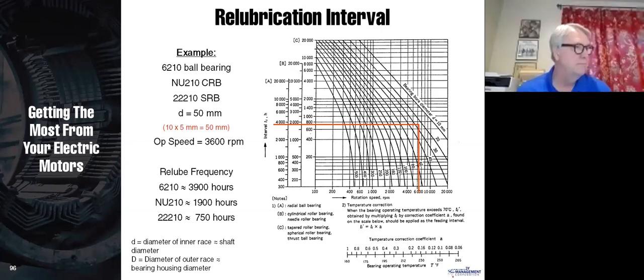Is it recommended to do body earthing on all types of motors? Yeah, so when we talk about earthing, I think here we got a European, but maybe that's getting more common in the US. So in general, in the United States, we talk about grounding, and that means connecting some conductive part to the earth. In Europe and other places, they call that earthing. It's the same thing. Not only is it recommended that you connect the frame of the motor to ground, it is a National Electrical Code requirement that you connect that frame to ground. So all frames of motors must be grounded or must be earthed. And the reason for that is if they're not, and you have a conductor accidentally touch the outside of the motor, and then somebody comes along and puts their hand on the motor, they could get electrocuted. So you always must ground the frame of the motor.